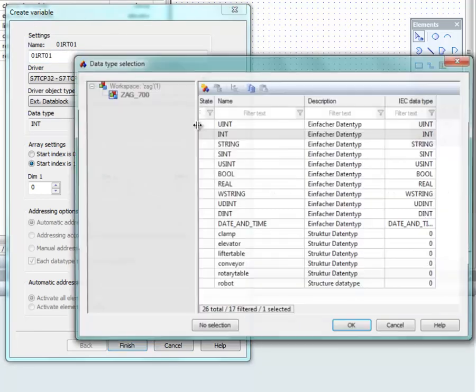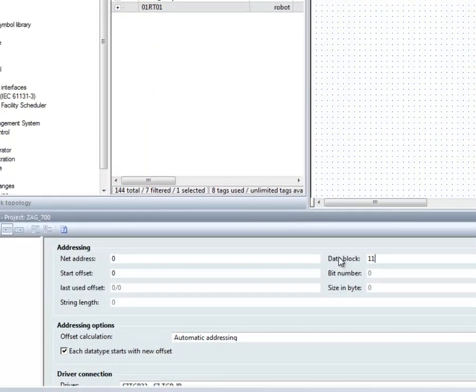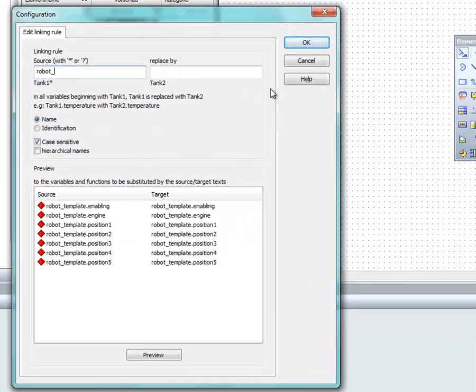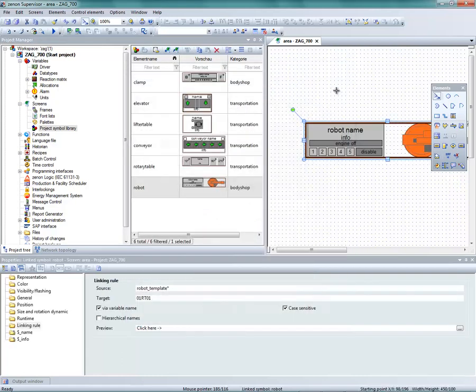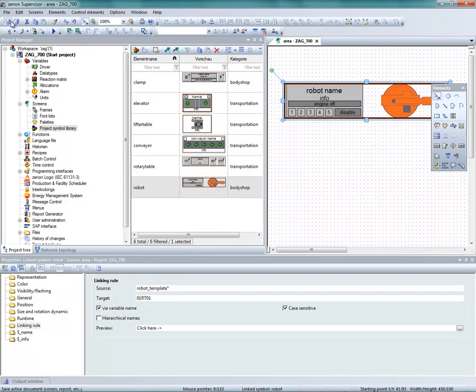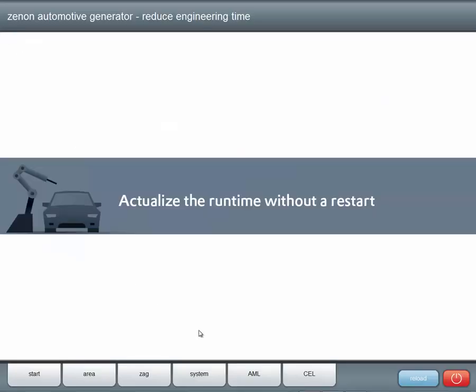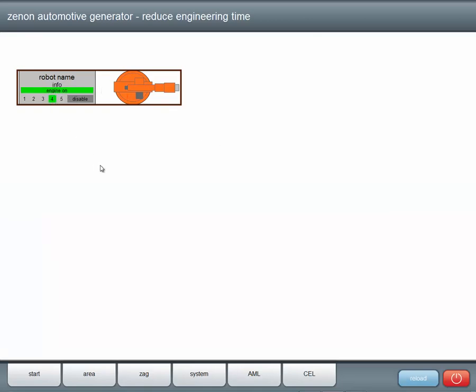We add a suitable variable in the Zenon Editor, choose the correct structure data type and address the variable. Then we add the symbol to the screen and replace the template variables with the robot variables. We create the runtime files and refresh the runtime without having to restart it. And by the way, this is a speciality of Zenon. The new element is now actively available.